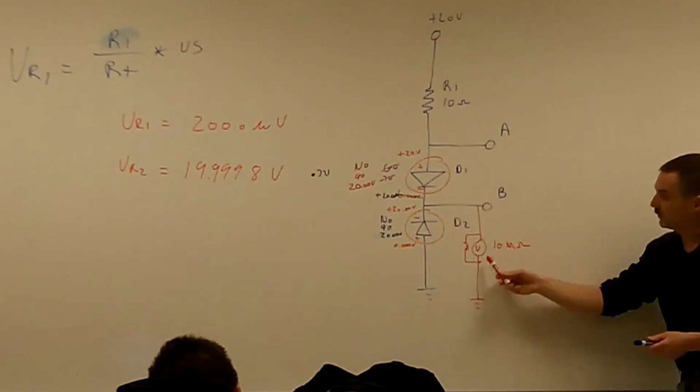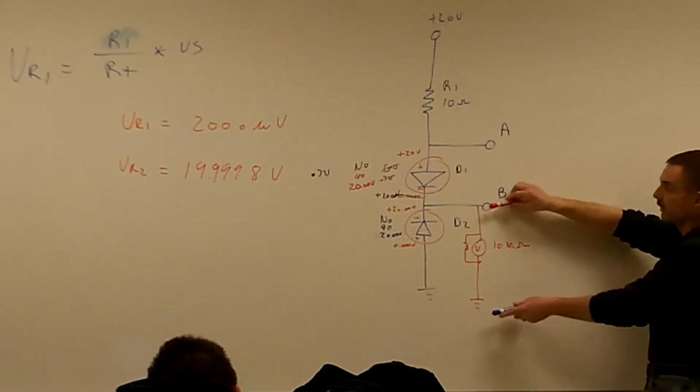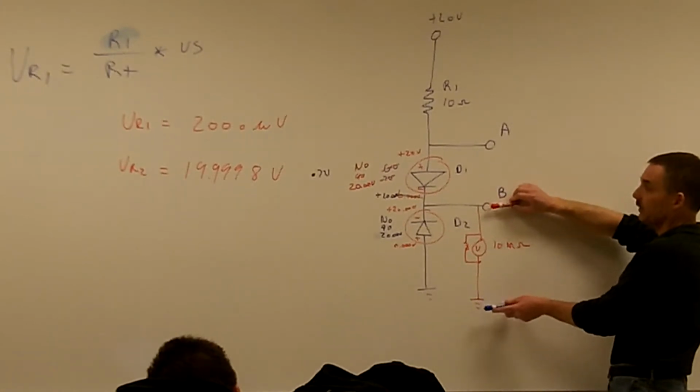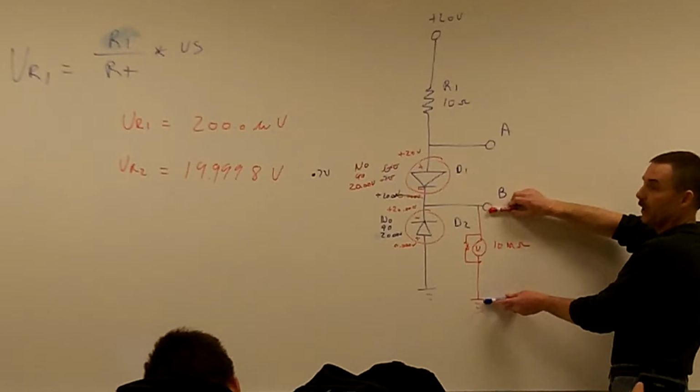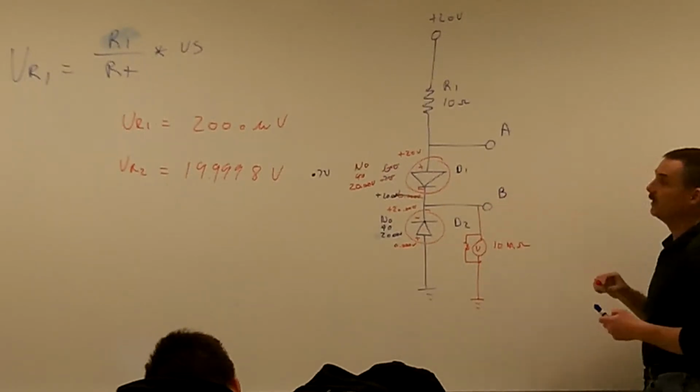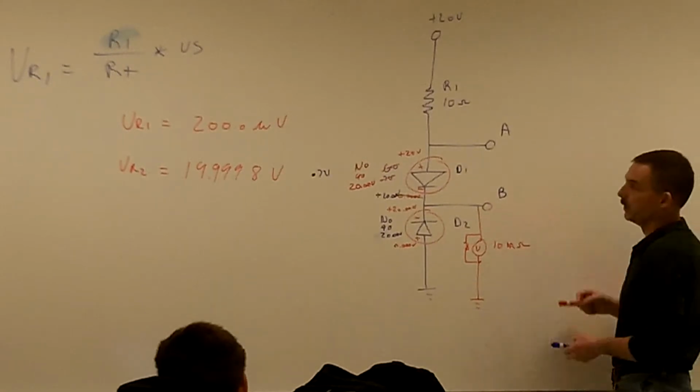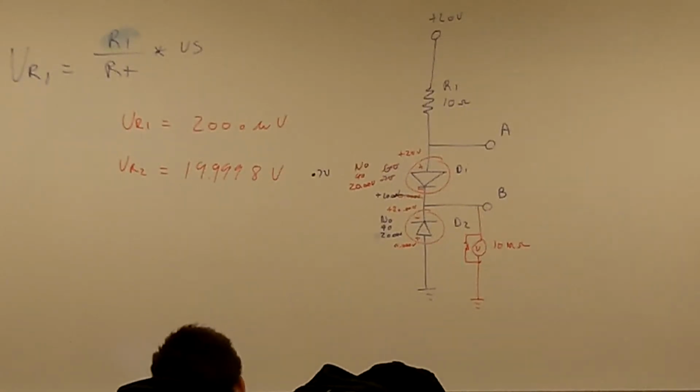So we have to be careful, because you can actually activate inputs and outputs, or activate inputs going into your solid state devices, just by putting in your voltmeter, and all of a sudden that machine can do some unexpected things. So you have to be careful when you're hooking up your voltmeter into your circuits.